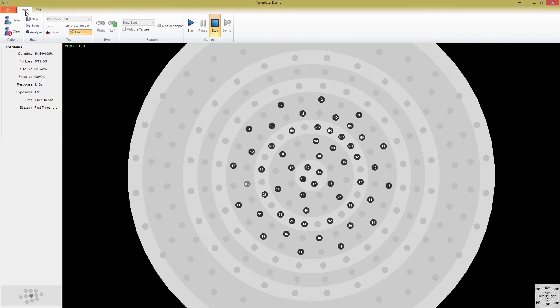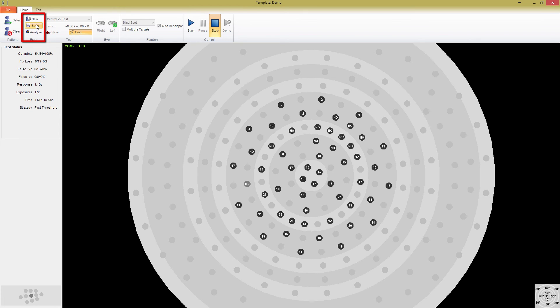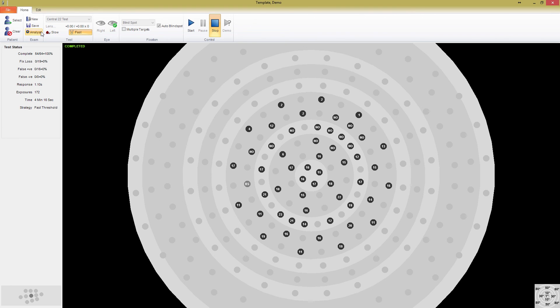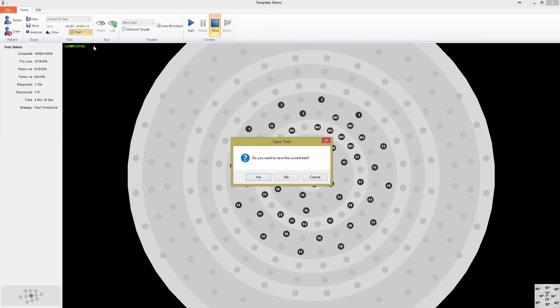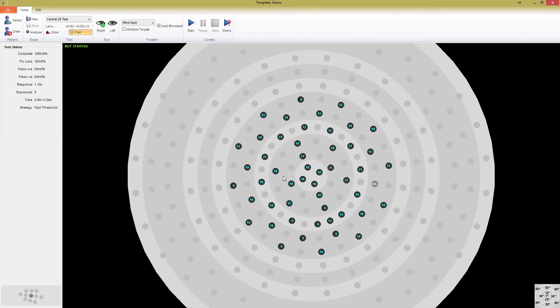Now the test is completed, and you've tested the additional points you're interested in, you can either analyze the test immediately, or save it. Press on save to store the test under whichever patient you have selected, or click analyze to take a look at the results first. To test the other eye, simply click on new. This will change the exam over. Be sure to patch the patient's other eye, move them onto the other side of the chin rest, and align them correctly. Click start to perform a test when you're ready.